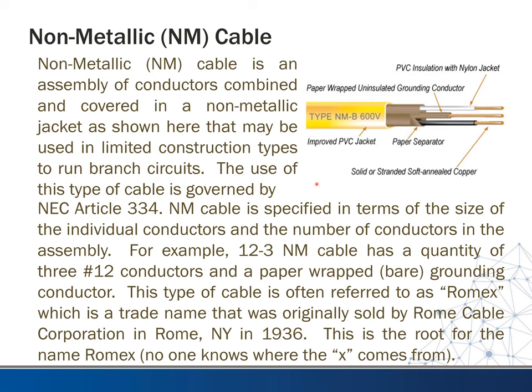NM cable is specified in terms of size of individual conductors and the number of conductors in the assembly. For example, 12-3 NM cable has a quantity of three number 12 conductors and a paper-wrapped bare grounding conductor. This type of cable is often referred to as Romex — that's the trade name. The history behind that is that it was originally sold by Rome Cable Corporation in Rome, New York in 1936, which is the root of the name Romex.